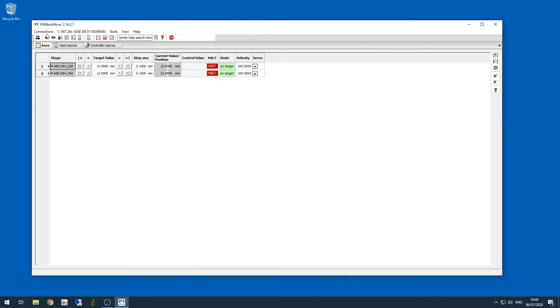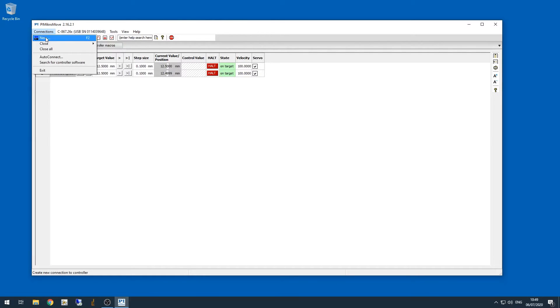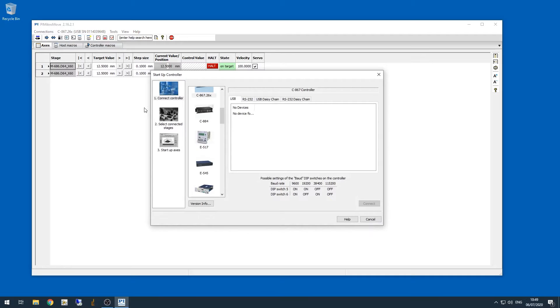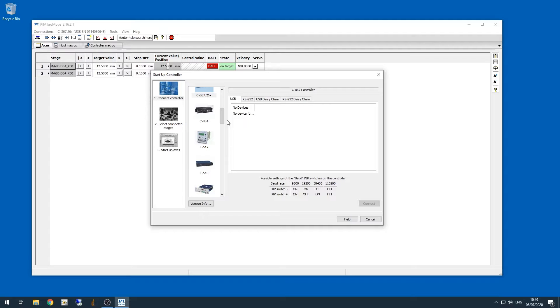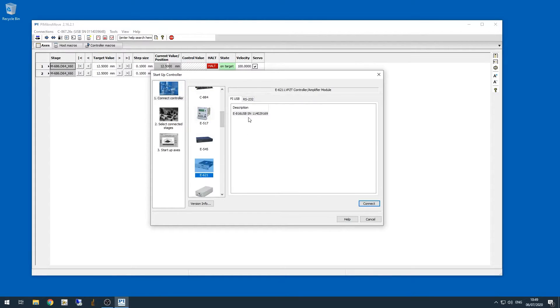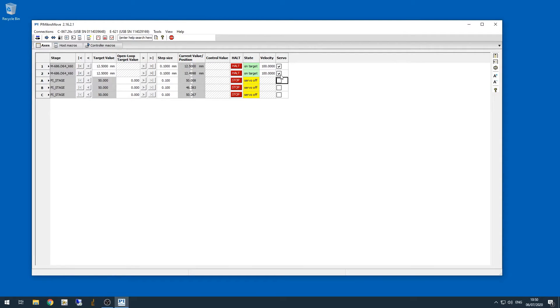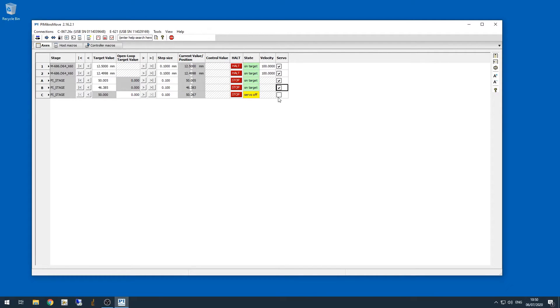Now let's try connecting with the controller that's holding the lower objective XY and the sample Z piezo stage. That will be the E621, which is inside of a larger chassis, so you get all three axes at once. These are all piezo stages, so after you click connect, you don't need to worry about doing any referencing. Now when you initially connect, you'll probably see that all the servos are off, so make sure that all the servo boxes are checked and they are on.